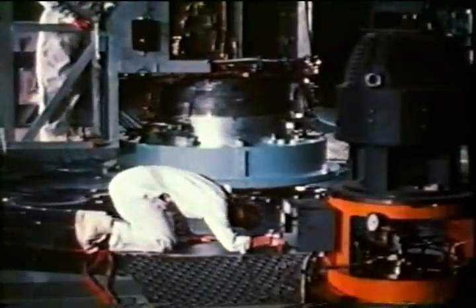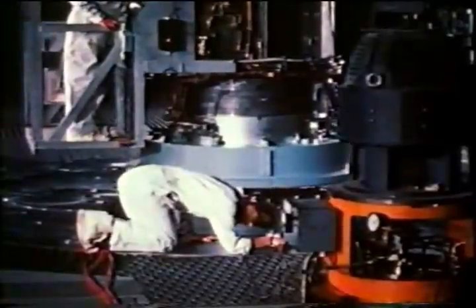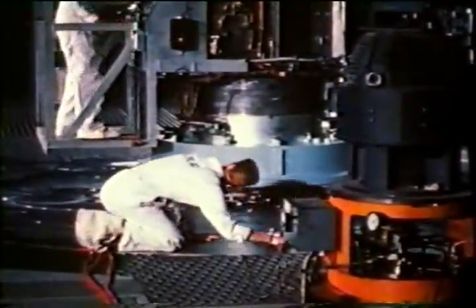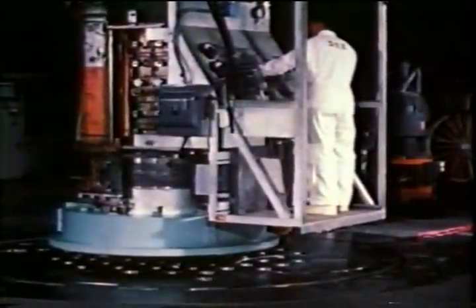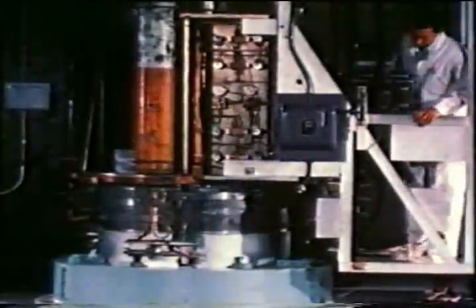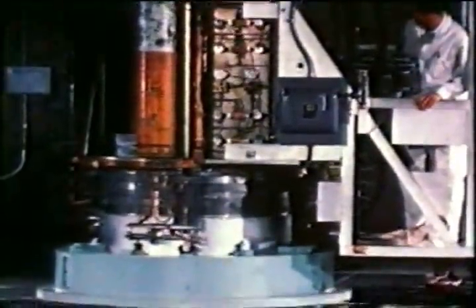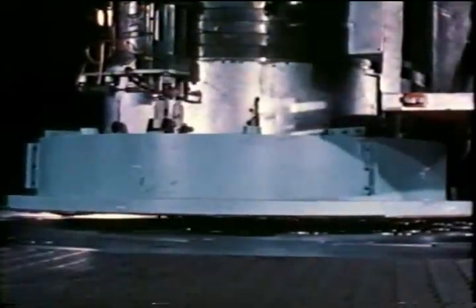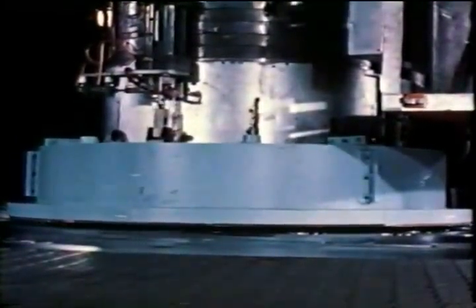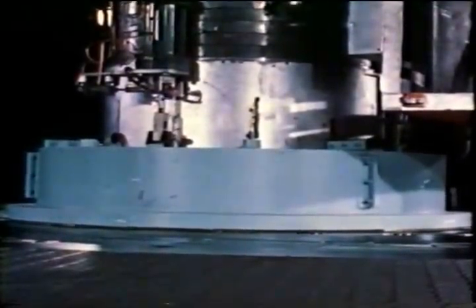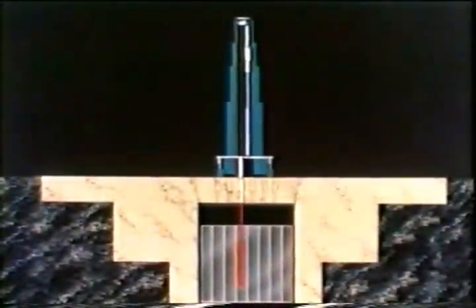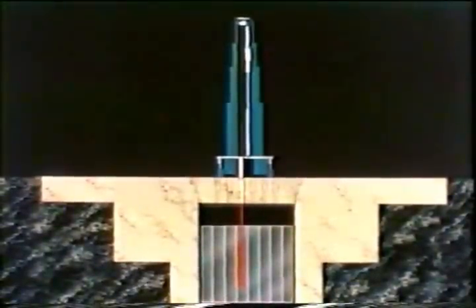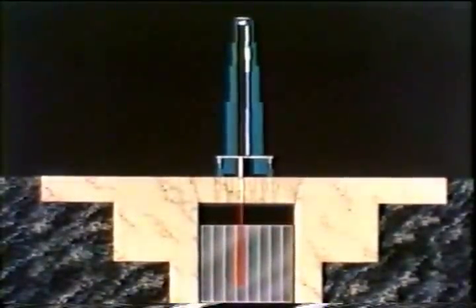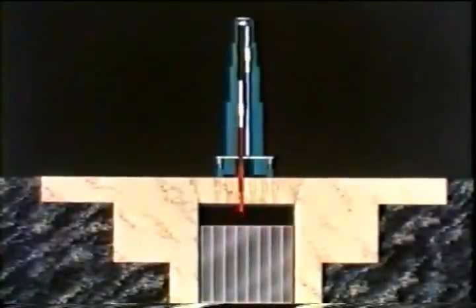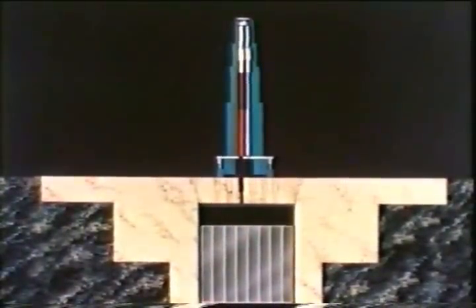The operator positions the cask in the general area over the used fuel element to be withdrawn. An indexing mechanism then guides the cask to a preset position, precisely in line with the given fuel element. A pneumatic mechanism forces a lead radiation shield down onto the surface of the loading face. A gas-tight seal is made prior to withdrawal of the fuel element. A pickup device within the cask is lowered to engage the shielding plug of the used fuel element. The shielding plug, hanger rod, and radioactive fuel element are lifted out of the core as one complete unit.